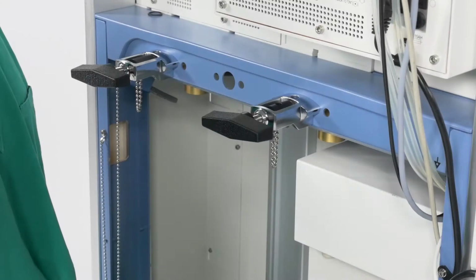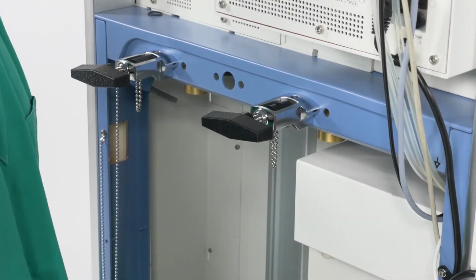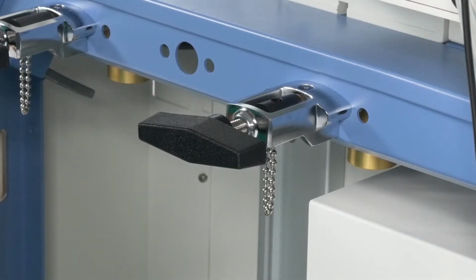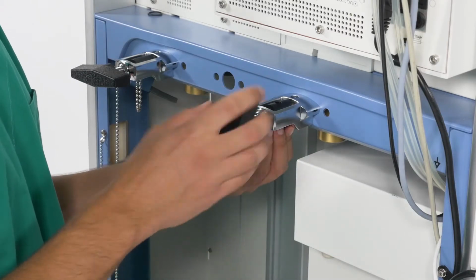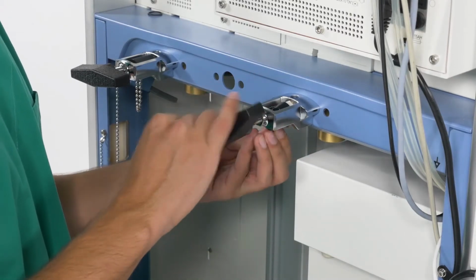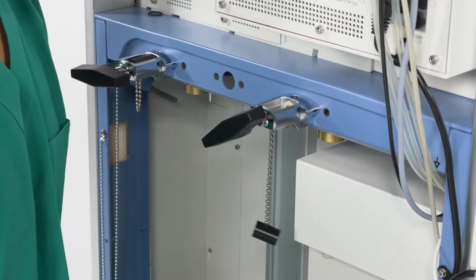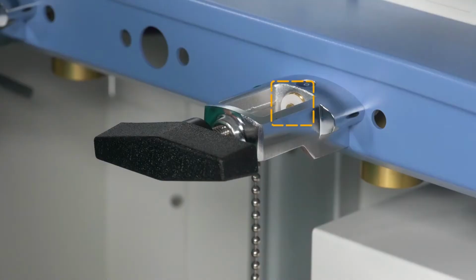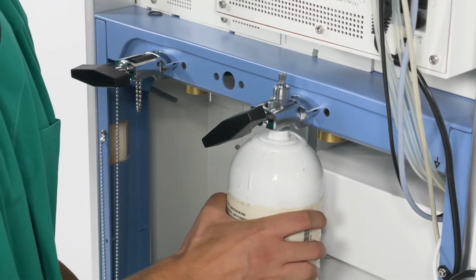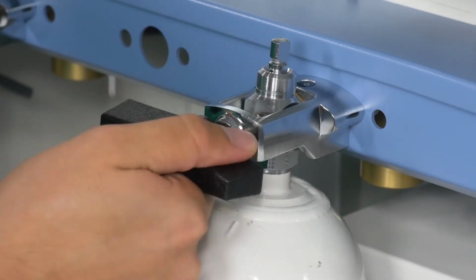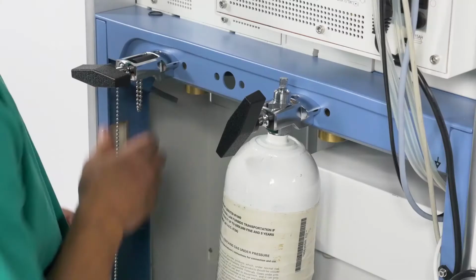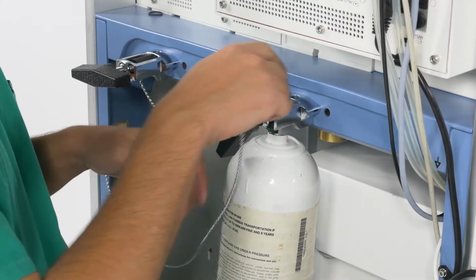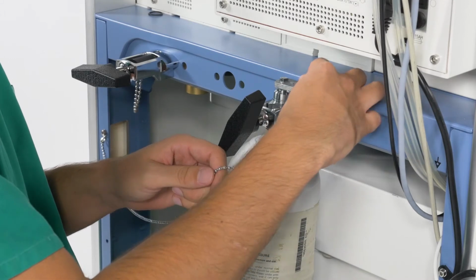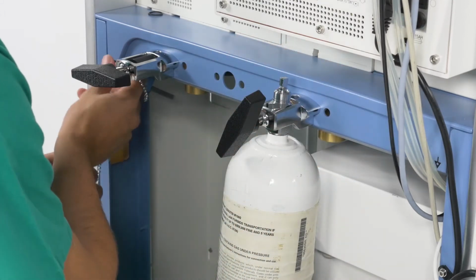To connect gas cylinders to the optional pin index cylinder supply on the back of the device, first remove the plug from the gas cylinder holder. Inspect the old sealing washer and replace it if needed. Make sure that both pin index pins are present below the gas inlet. Then insert the cylinder head from below into the cylinder holder and allow the pin index pins to engage in the pin index holes. If required, the gas cylinder valve can be opened with the supplied wrench.